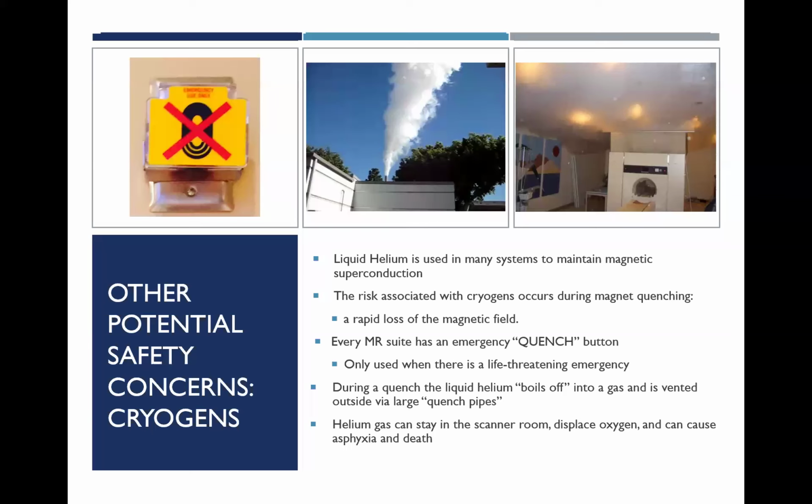Other potential safety concerns include cryogens. Liquid helium is used in many systems to maintain magnetic superconduction. And the risk associated with cryogens occurs during magnet quenching, which is a rapid loss of the magnetic field.